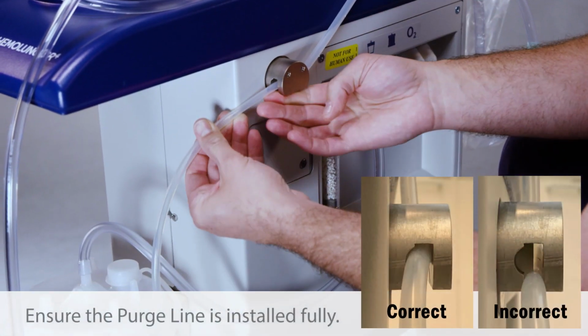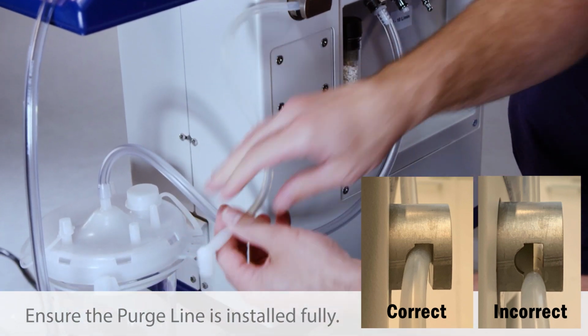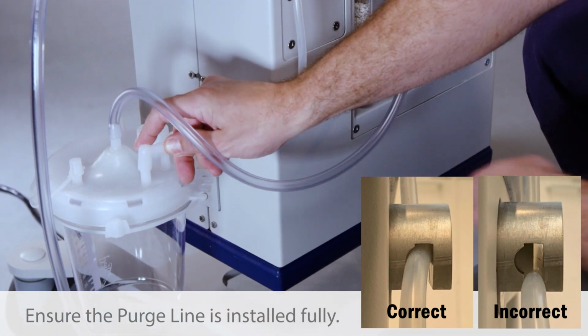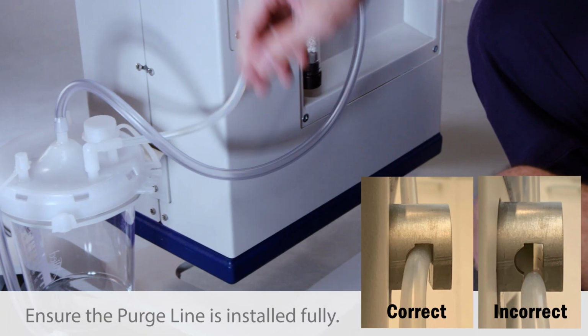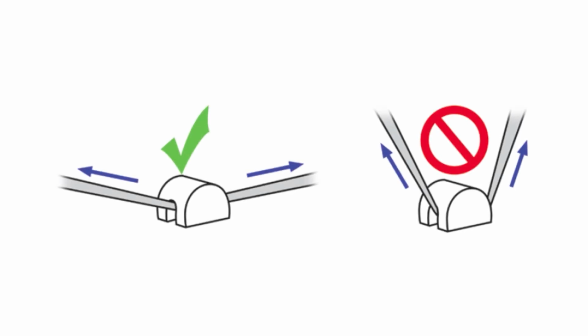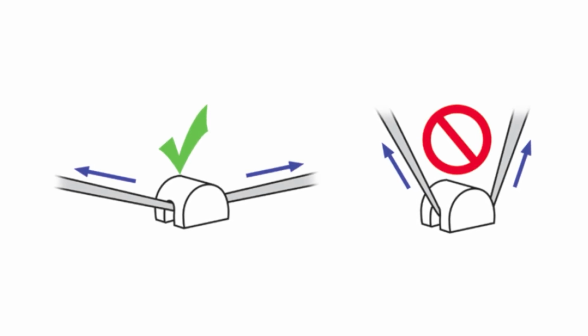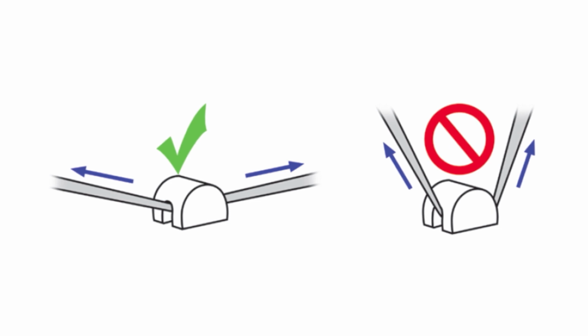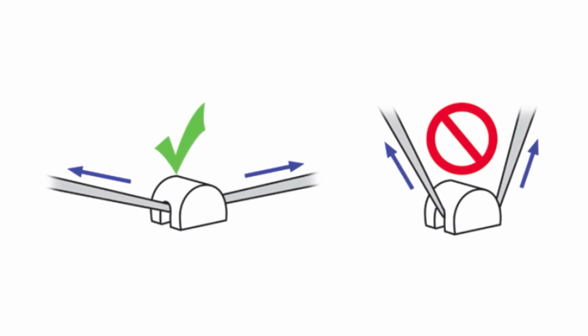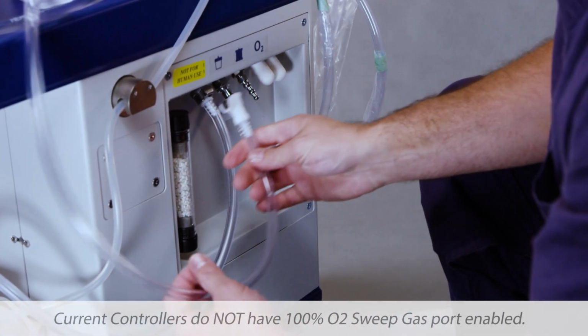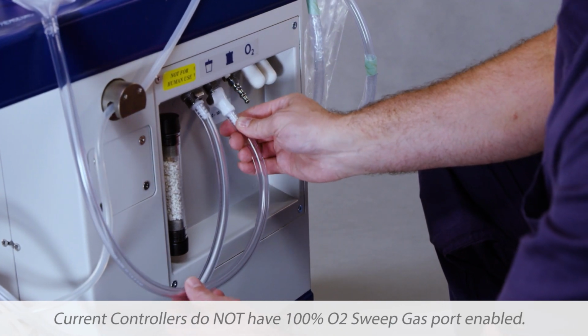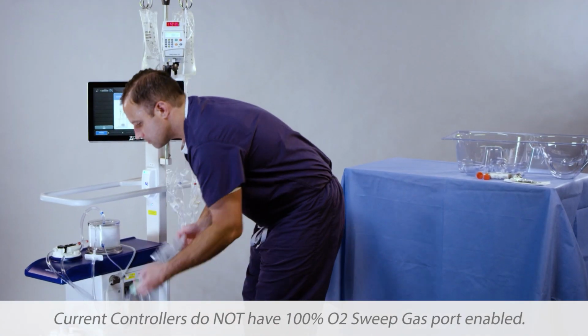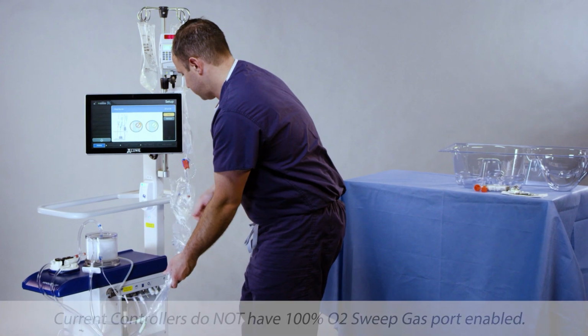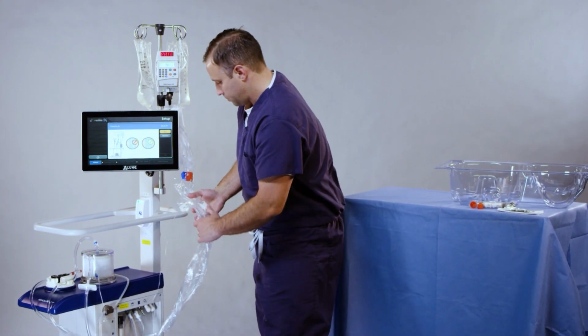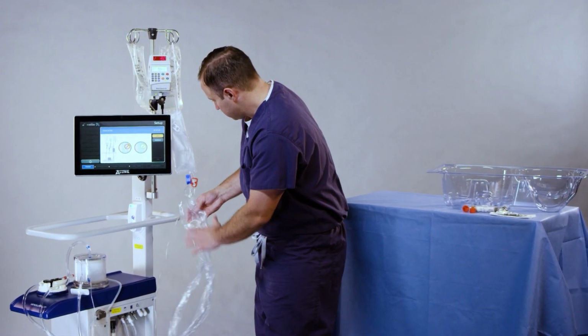Install the silicone sweep gas tube from the cartridge into the purge valve. Then connect it to the vacuum canister port labeled Patient. Use care when placing the silicone tubing into the purge valve. Using too much force or excessive stretching can cause damage to the tubing. Now connect the sweep gas supply tube with the bacterial filter to the controller. Make sure all tubing connections are completely secure and there are no air or fluid leaks observed in the circuit.